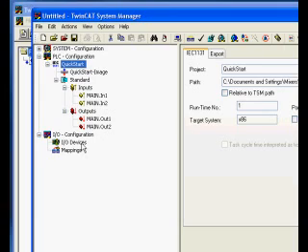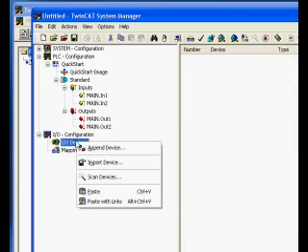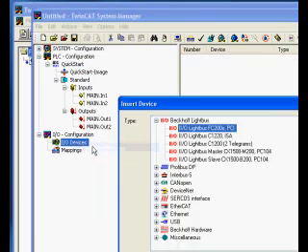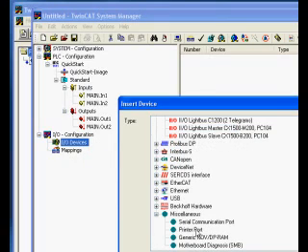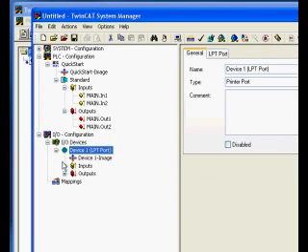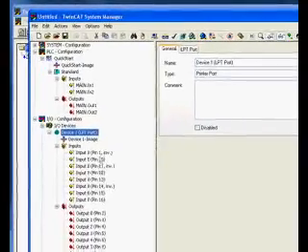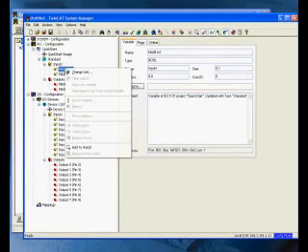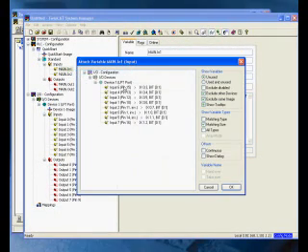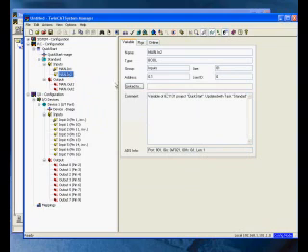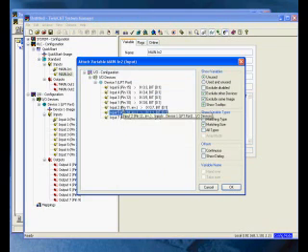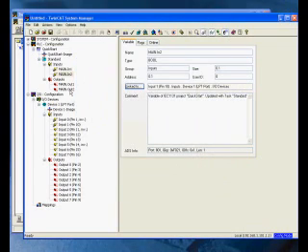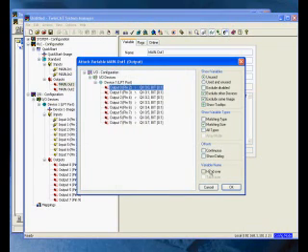So now let's go down and add some hardware. TwinCAT will let you use your parallel port, fortunately, so you do not actually need any hardware. So I'm going to right click and add a new device, and you see under miscellaneous I'm going to pick parallel port, and now you can see it will give me options of using my pins on my parallel port as physical I/O. So now I'm going to right click on my In1 variable, change link, and pick input 0, link it to that. Now I'm going to show you can also come over here and use the button here, which does the same thing, and I'm going to link that one to input 1.